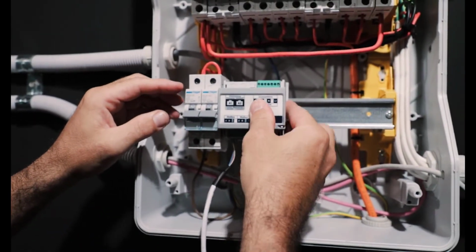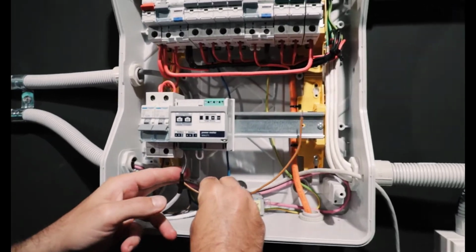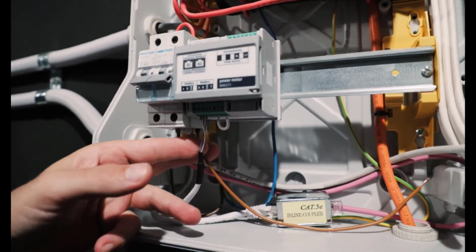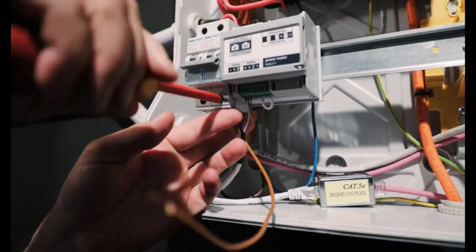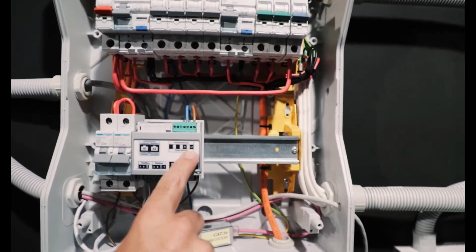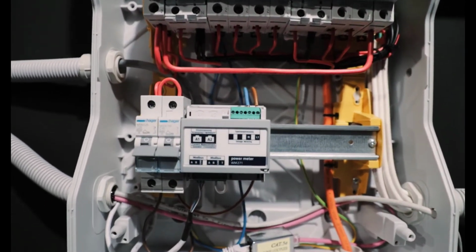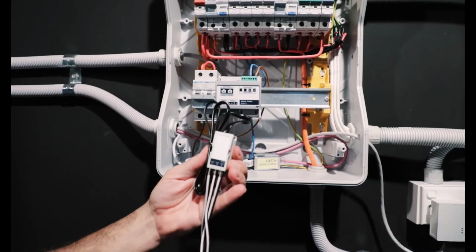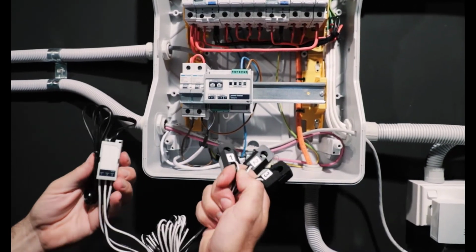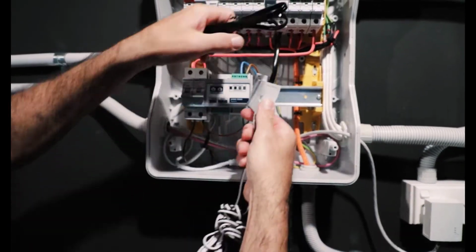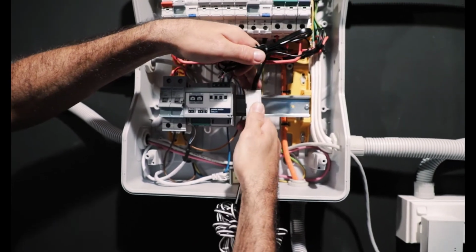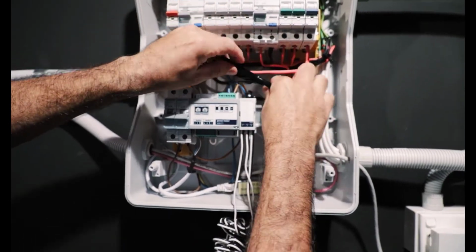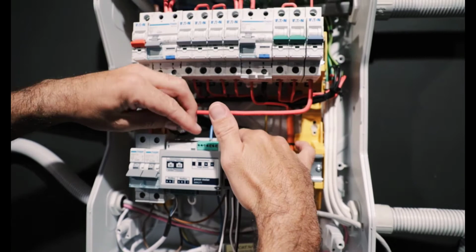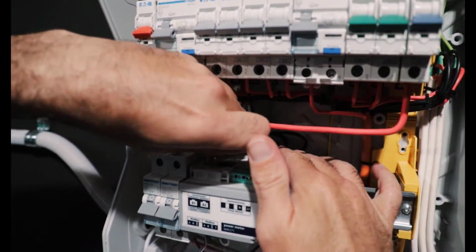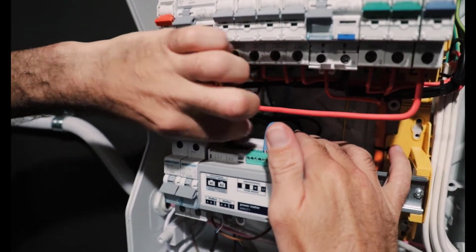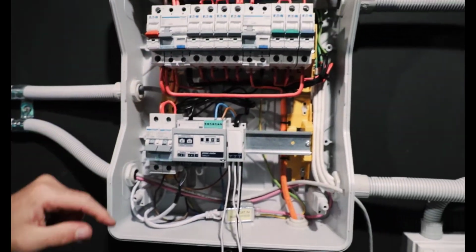Meter comes on. We get the meter wired up. And then what we will be doing in this installation is we're going to be having both sets of CTs, or two sets of CTs, one measuring the loads, the consumption, and one measuring the production. Okay, so the CT set, the transducer, what the transducer is basically doing is bringing all of that measurement value into one Modbus signal, which goes into the meter.